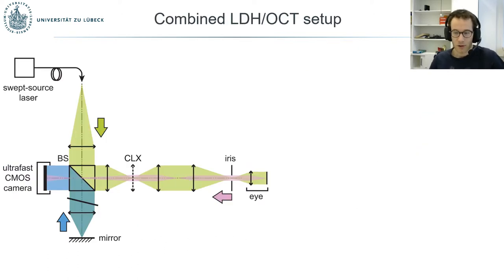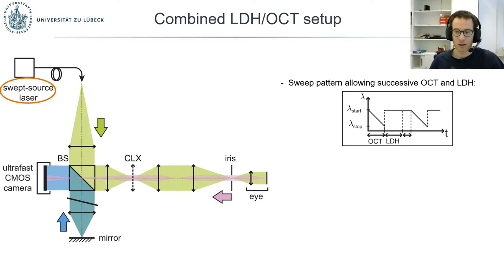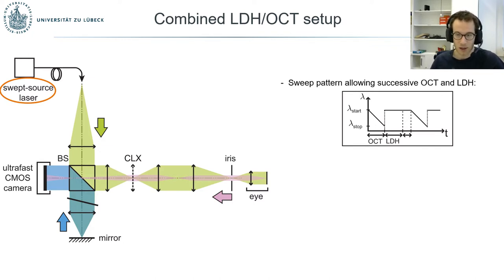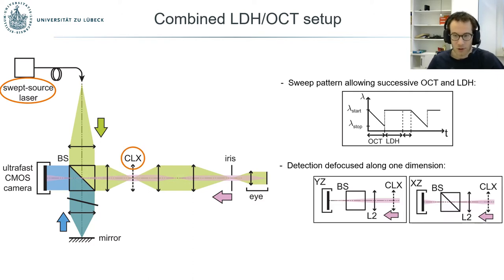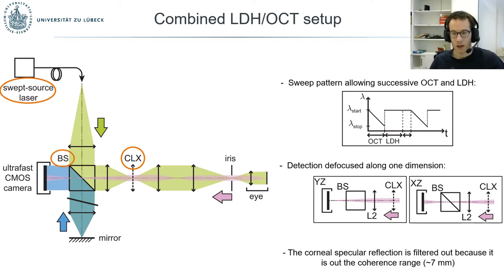Here is the setup we use to combine both modalities. The swept-source laser used for OCT can naturally alternate between OCT and LDH imaging, because at the end of each sweep the laser positions itself on the starting wavelength and remains stable there. That stable-wavelength time can be used to perform Doppler imaging, making it simple to alternate between the two modalities with the same light source. We added a cylindrical lens to introduce defocus along one dimension, preserving sharp lateral contrast for live preview on one dimension while benefiting from defocused detection on the other. A normal beam splitter cube could be used because the specular reflection from the cornea was simply out of the coherence range.